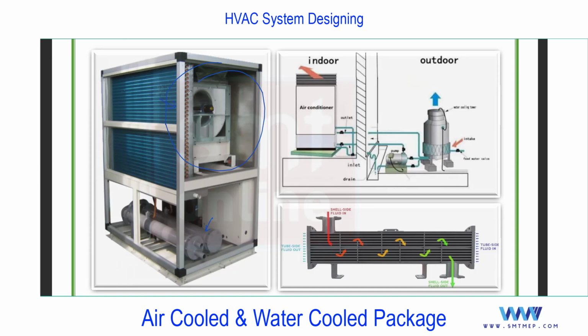Can you find different types of heat exchanger? You see, this is also a heat exchanger. This evaporative coil is also a heat exchanger. This is a tube and fin type. You'll find different types of heat exchangers, which can be used to reject heat or extract heat, depending on the application. Similarly, this is a shell and tube heat exchanger. In the water cooled package, we are using this heat exchanger for the condensing side, so we call it a shell and tube condenser. Try to understand the concept for this condenser side.